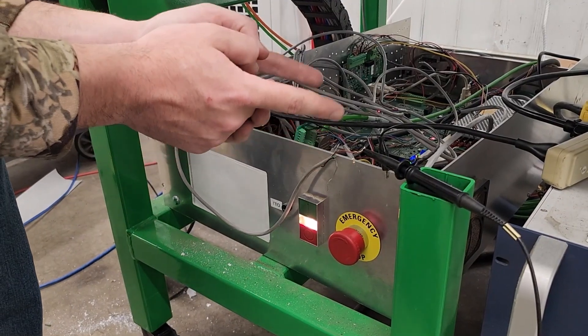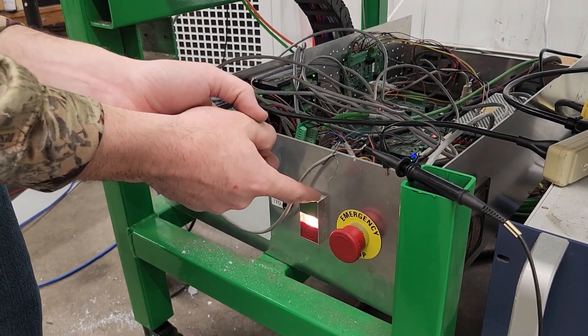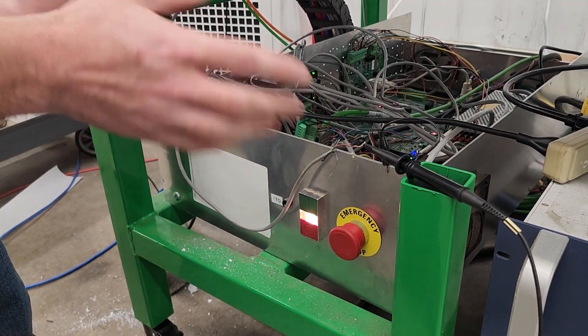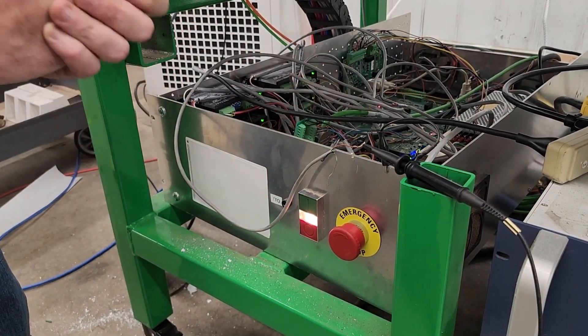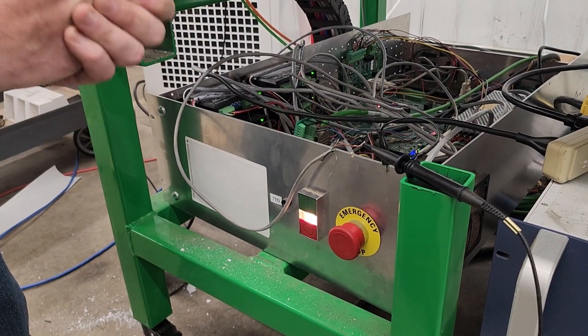Really, we don't need to ground shielding on both sides. As you saw, we just have the one side connected on this cable, and that cleaned everything right up. So we just need at least one side of the shield on one end of the cable connected to the ground.